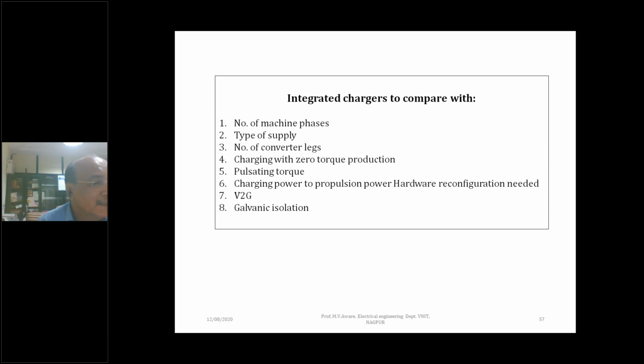We have to manage this. On one account, the motor will give more reliable operation, and the inverter will definitely have more components, but their thermal stress is quite low, because per-phase current, which is the inverter component current flowing at the rated value of motor, is less. So you are not stressing your switches to very high currents, and the losses and other issues can be contained.